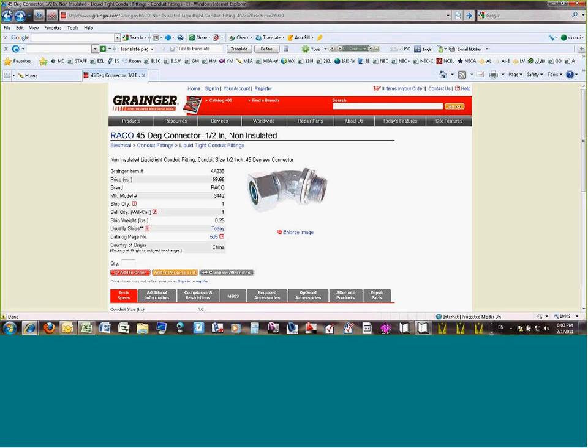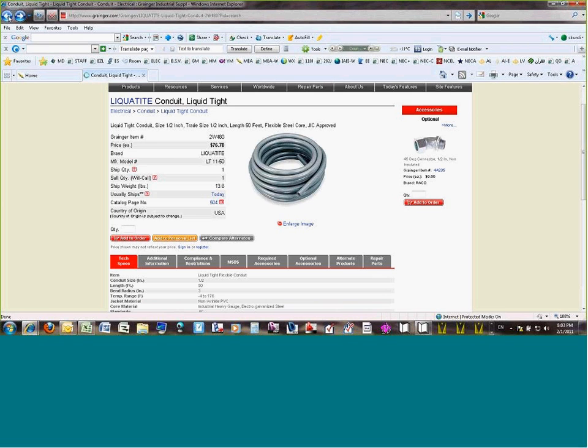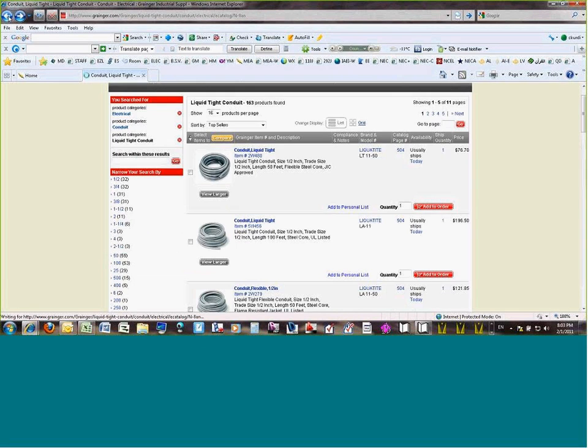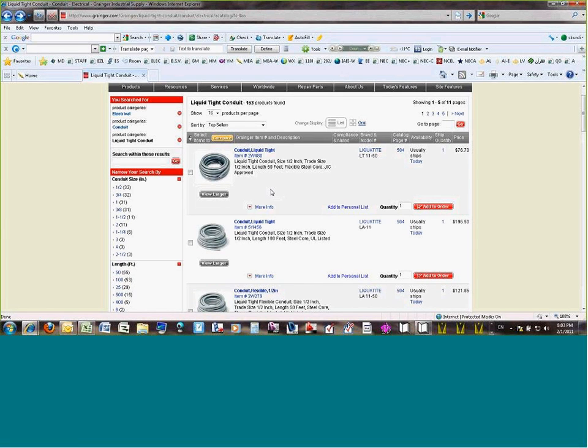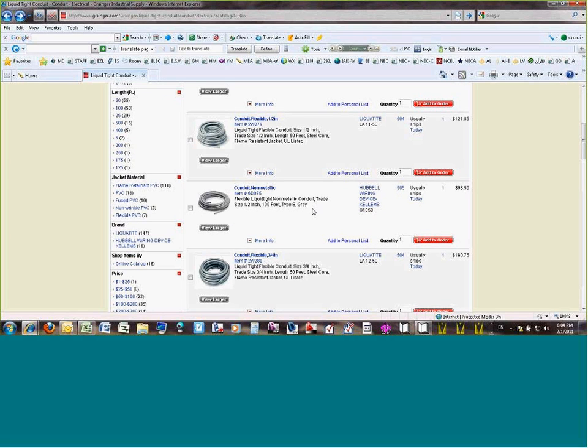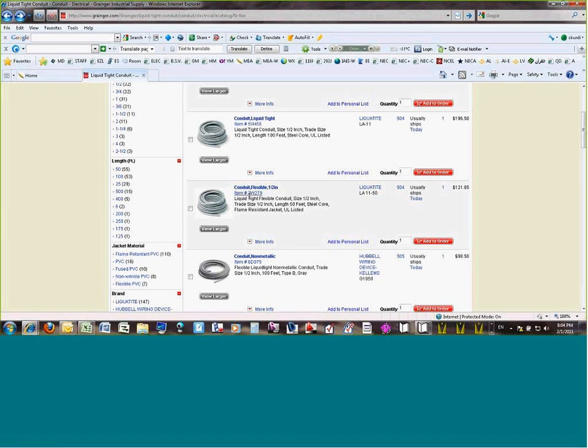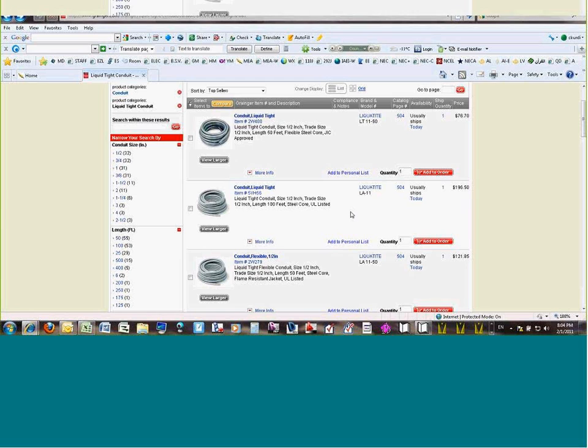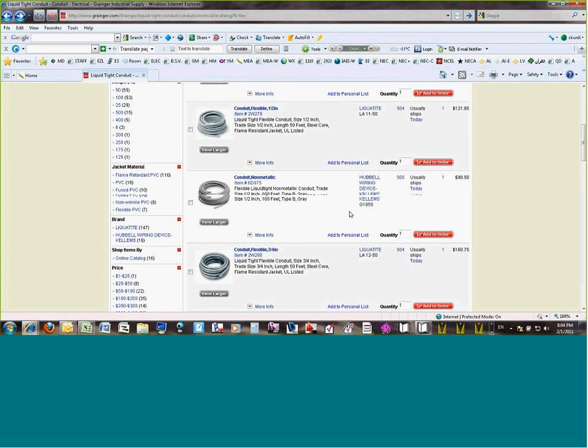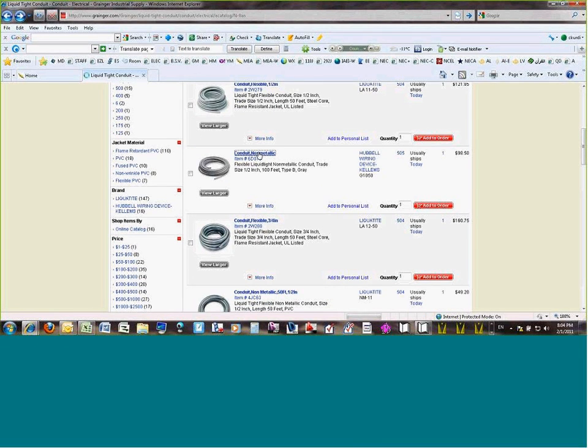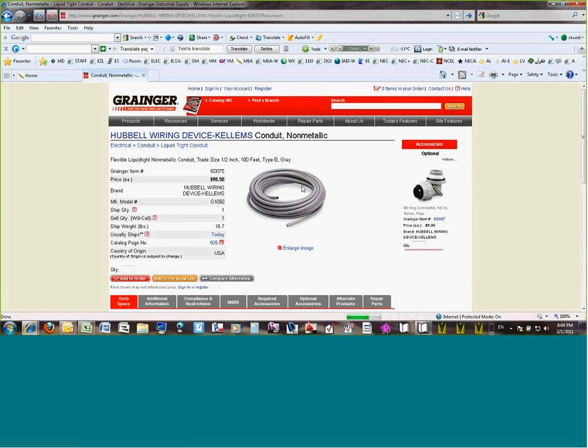All right, these are a couple of connectors that come in handy with this type, looking at 73 for 50. Okay, so the Liquidtight is steel, all of it is steel. If you look at it, most of it or all of it is steel, Liquidtight flexible non-metallic aside. If it's Liquidtight, it's steel because it's going to be a wet location. You don't want to put aluminum in a wet location. So for the most part, it's steel. Here's the Liquidtight non-metallic conduit, guys. That's the last one that we talked about.